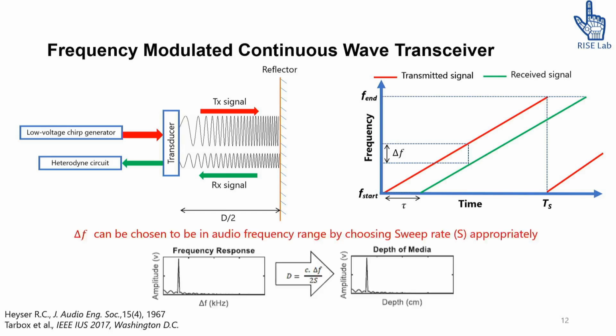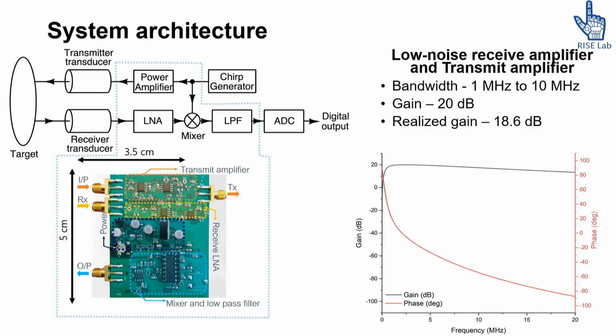And by using a simple FFT after the heterodyning, we can transform this amplitude versus delta F, or frequency difference, plot to a typical A-mode plot, which is a depth versus amplitude plot. So you get an A-mode image simply by doing an FFT of the mixed signal. But the catch is that you have to choose the sweep rate very carefully such that this delta F doesn't fall into the megahertz range. Then you're still stuck with the same kind of problems. So you have to choose the sweep rate appropriately so that this delta F comes down to the audio frequency range or lower. So we designed a small system for wearable applications like the ones we discussed here in order to realize this, with the ultimate goal of an on-chip realization.